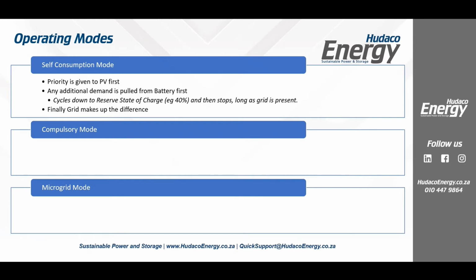The second thing is we will pull power from the battery to run any other loads on self-consumption until it reaches a reserve state of charge. Now, it's very important that we talk about the reserve state of charge. The SOC is not the battery's operating window. Remember, we always talk about 9.6 kilowatt hours or 12 or 16, whatever it is, as usable energy. So we can set the amount of usable energy.